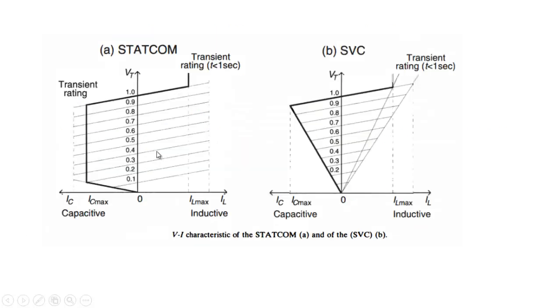This is shown in the practical VI characteristics of the STATCOM. Up to about 0.15 per unit it acts as a capacitor, but beyond 0.15 it is capable of drawing the same maximum current Ic_max at all voltages from 0.15 to 1 per unit. The linear operating range runs from one reference point to another. For the SVC, by contrast, the current increases or decreases as voltage changes from 1 per unit down to 0.